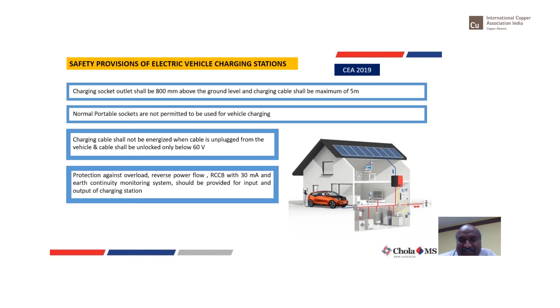Fine. Next is on the protection against overload, reverse power flow, RCCB with 30 milliamps, and earth continuity monitoring system. All these should be provided at the input and outgoing charging stations. Input could be some DB, and from the DB it comes to, say, a parking lot area where you have the outgoing station from where it connects to the vehicle. Ensure that all those protections are available.